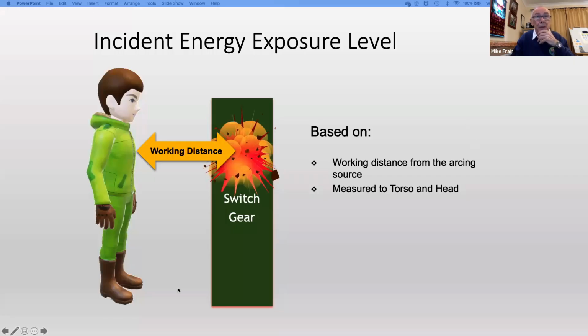So here we go, this is an incident exposure level. And as you can see here, this chap is standing at a working distance. It's a working distance from the arcing source that we take into account when we're looking at incident energy levels. And it's normally measured to the torso and the head. And the result of that is historically, that's where the measurements are, because the severity of a burn is affected by the amount of the body which is affected by the burn itself. So as it happens, the more of the body that is burnt, it lowers the survivability rate, as does age, by the way. So me getting into an arc flash incident is not a good idea, I don't think.